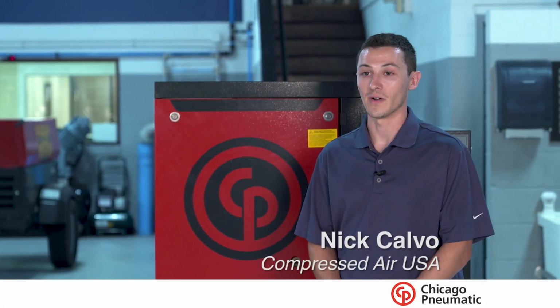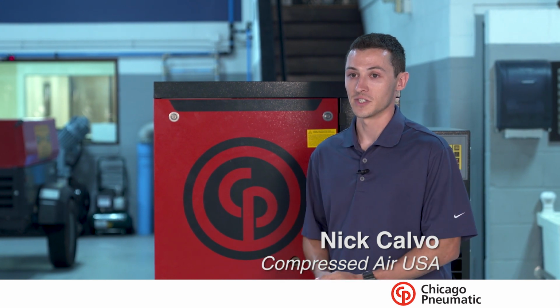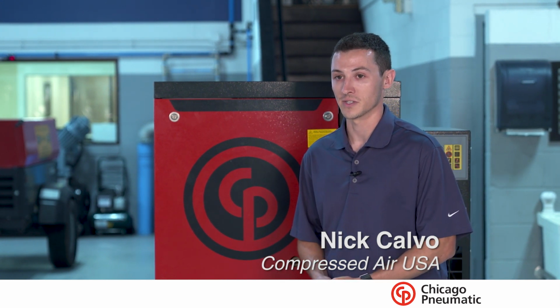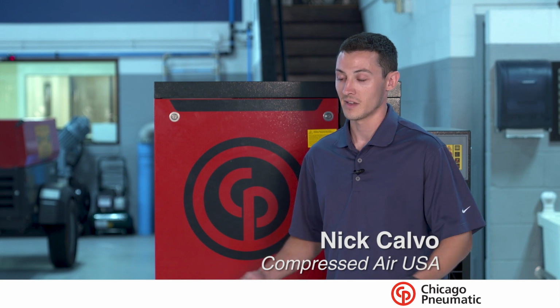Welcome back. We want to talk about air leaks. Air leaks are essentially just another demand on your air compressor, except it's not being useful for anything. So if you have mismatched fittings, or rubber hoses that are worn out and have cracks in them, and just small little bits of air, it's going to put a higher demand on your compressor, and that air is not going to you, it's going to the atmosphere.